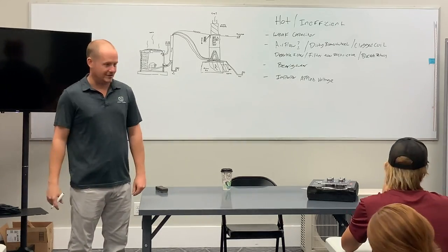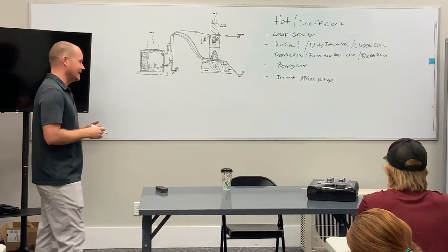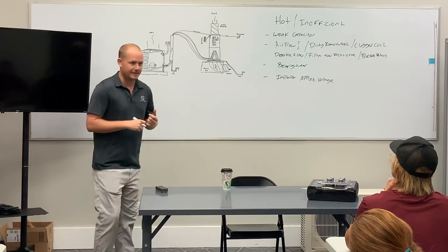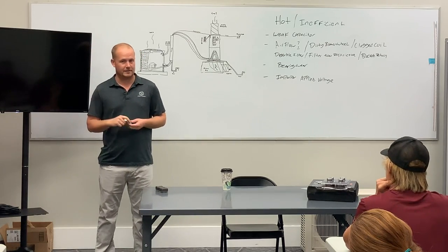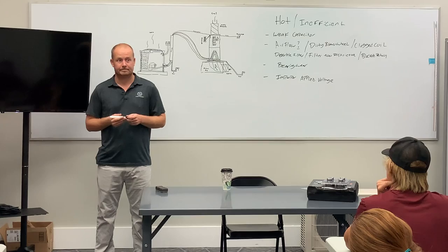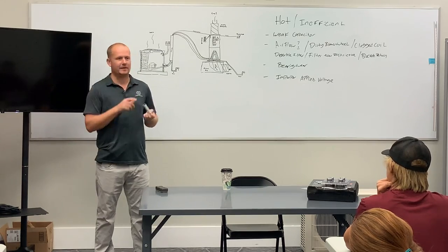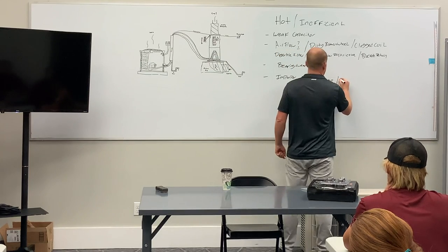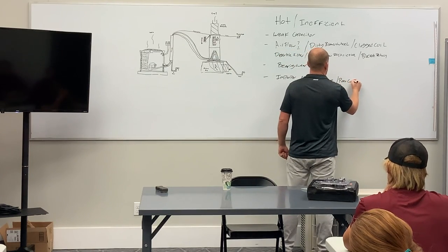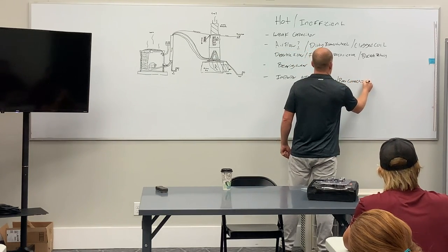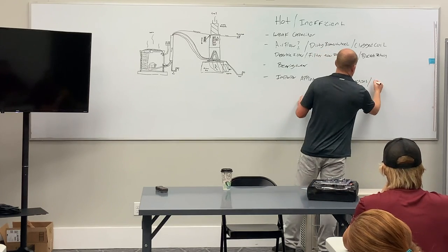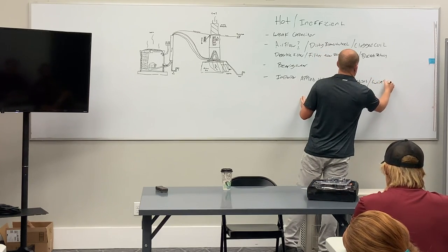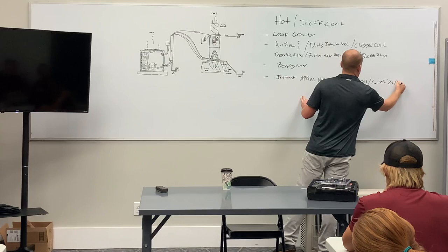Improperly sized wires. Improperly sized conductors. That could cause it. What else can cause that? It's not just sizing. What else? Wire length. There we go. All right. So we've got a list of things here. Poor connections, wire size, and length.